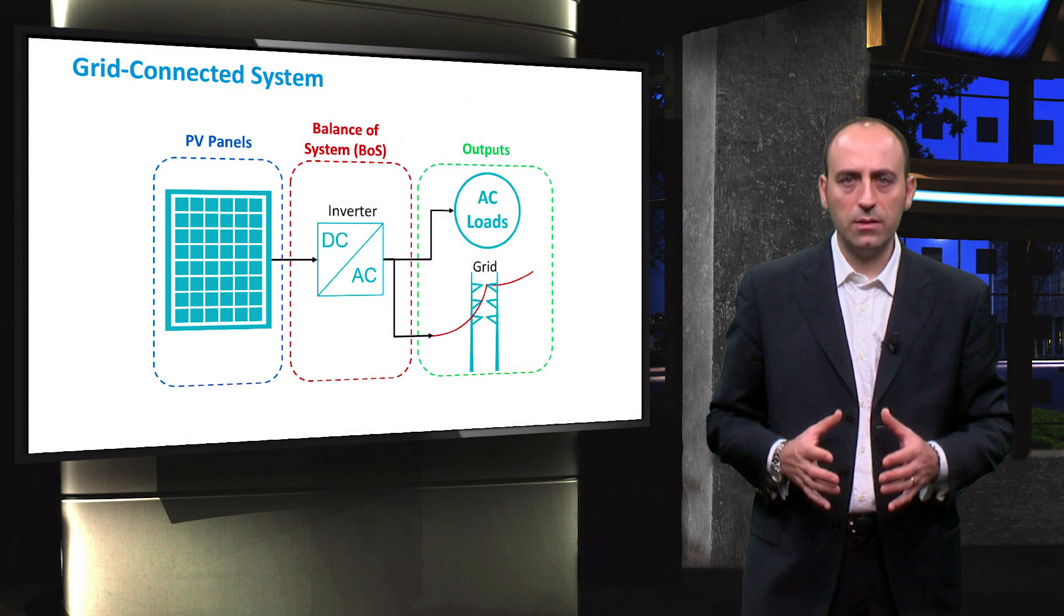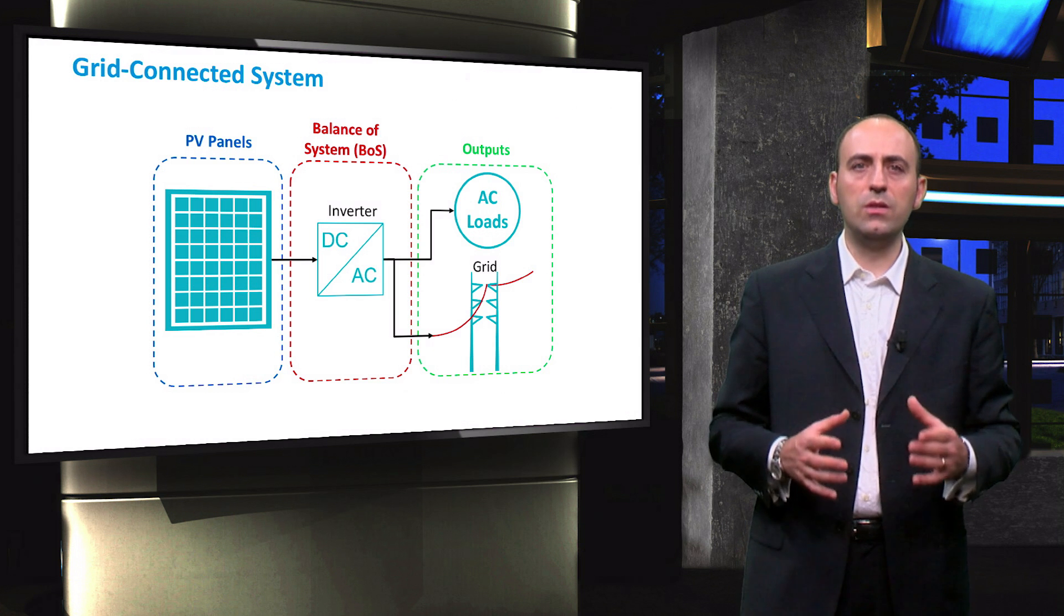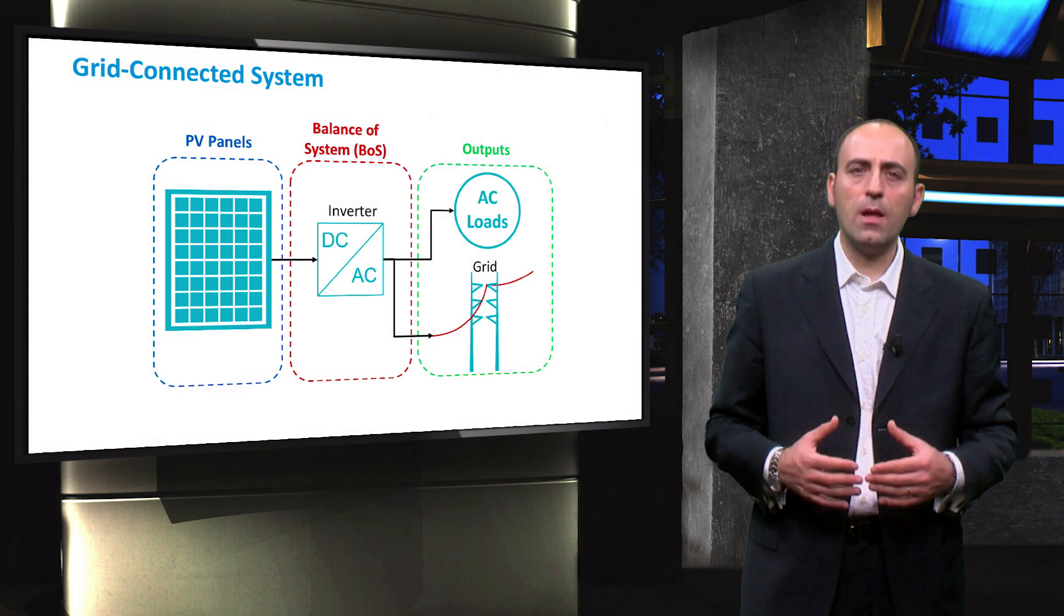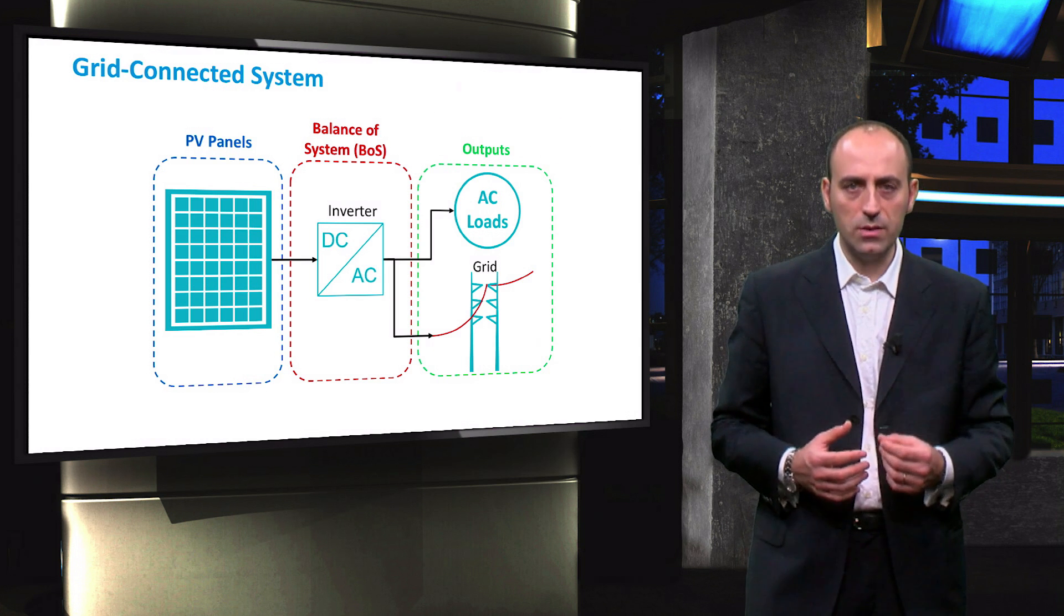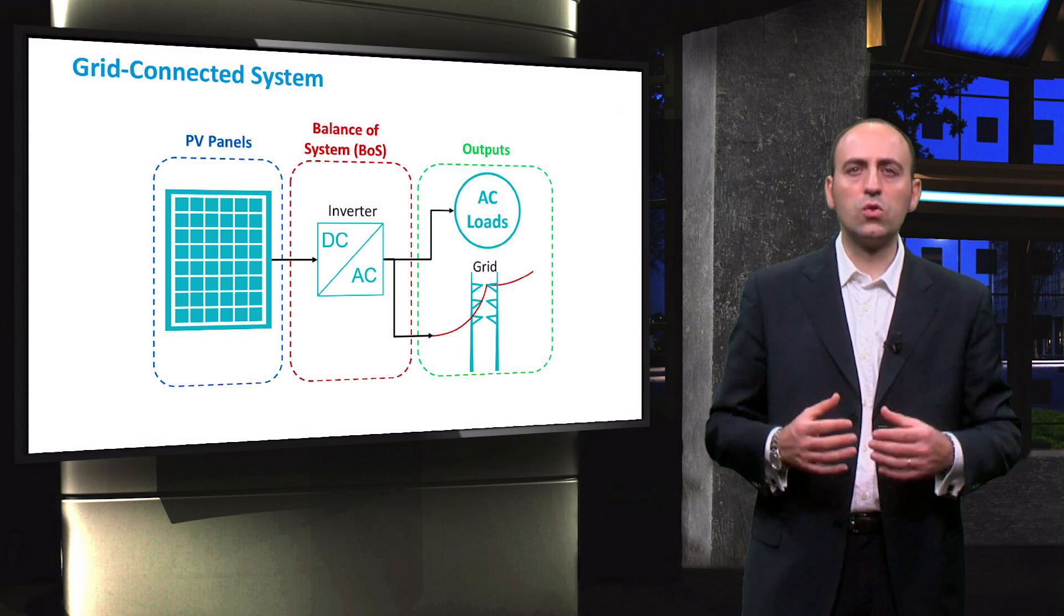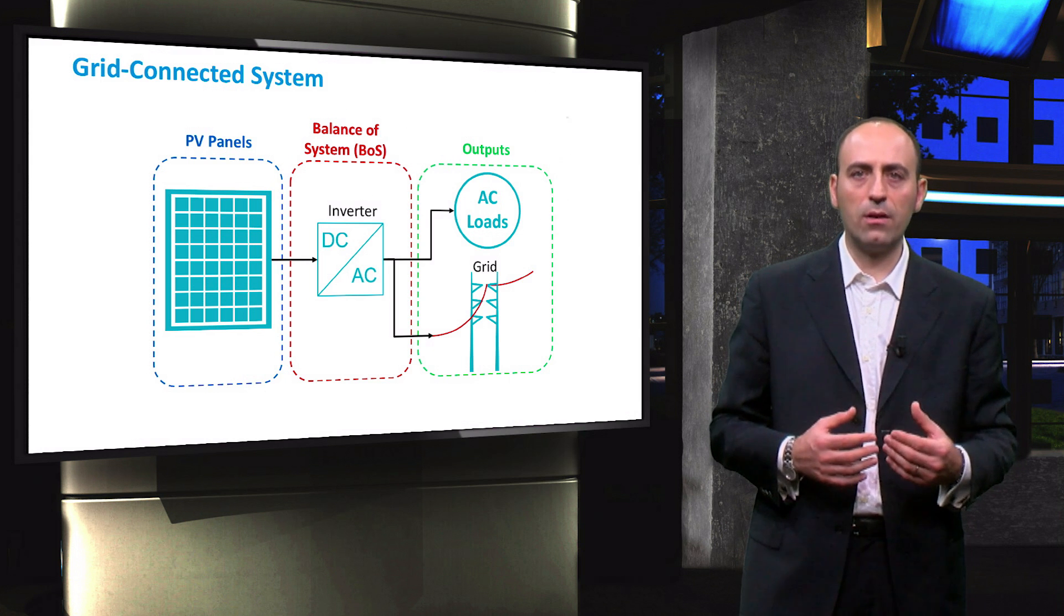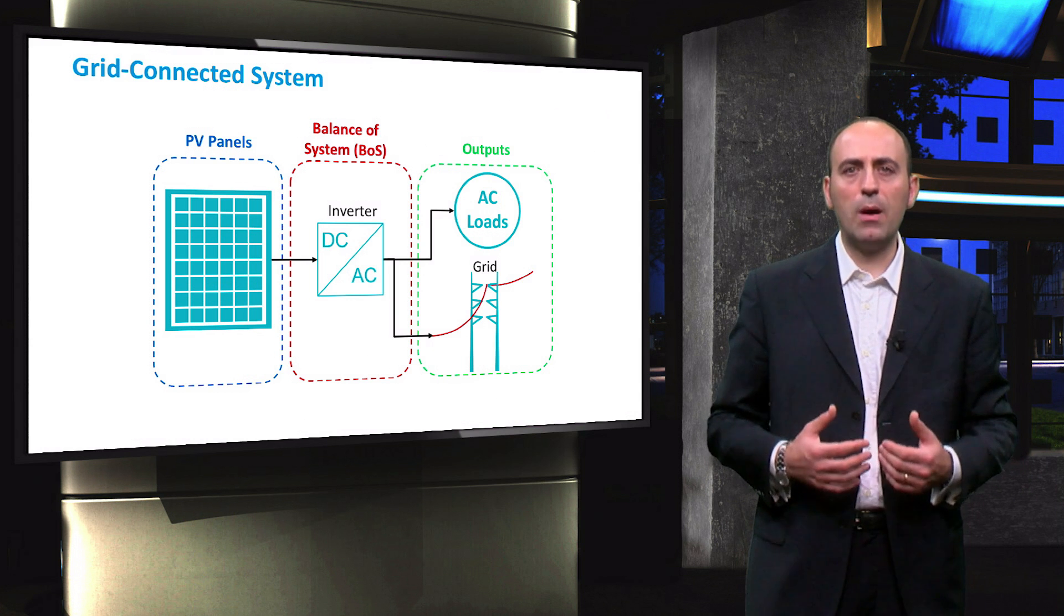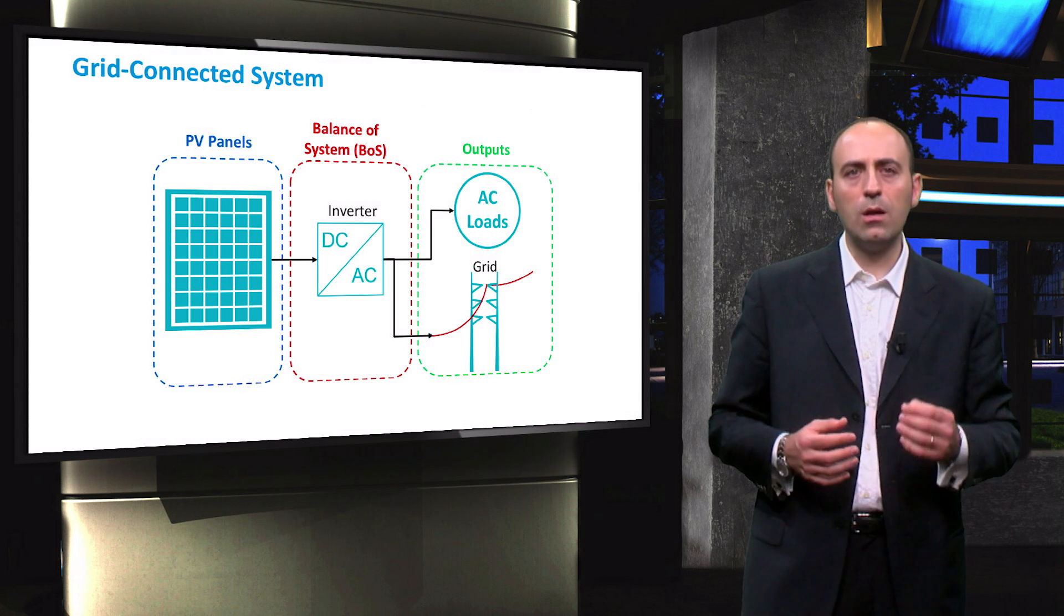In a grid-connected system, the inverter is connected directly to the PV array and converts the DC electricity coming from the PV array into AC electricity. Besides, such an inverter usually contains a maximum power point tracker system. As such an inverter is connected to the electricity grid, it must also synchronize with the grid, meaning that the phase angle of the AC signal coming from the inverter must equal to that of the grid. In order to increase power quality of the grid, the injected signal should also have a minimal harmonic content.